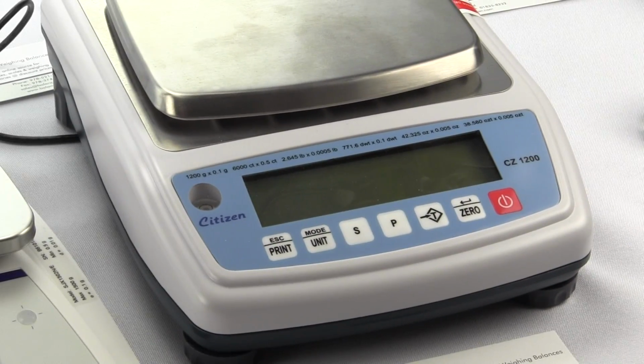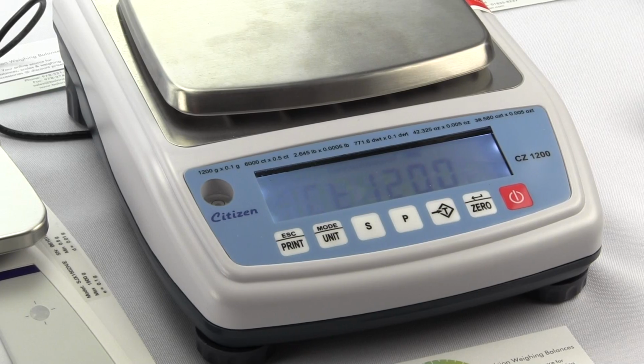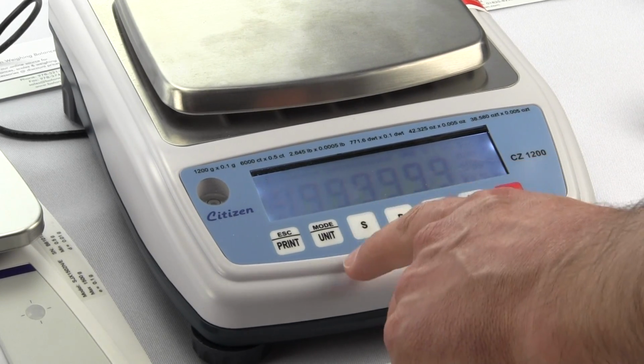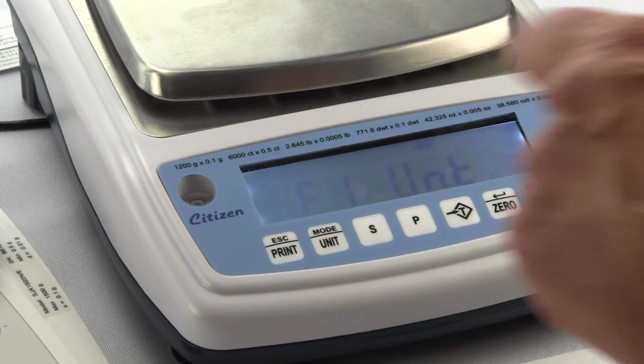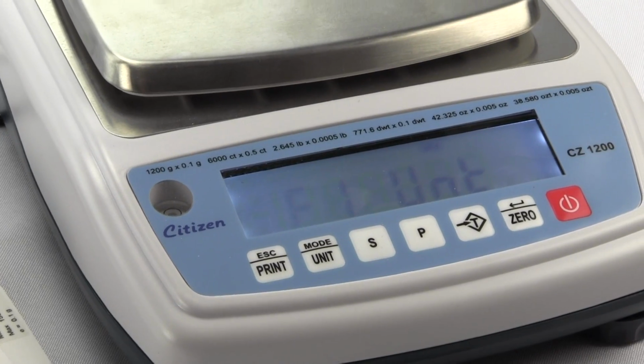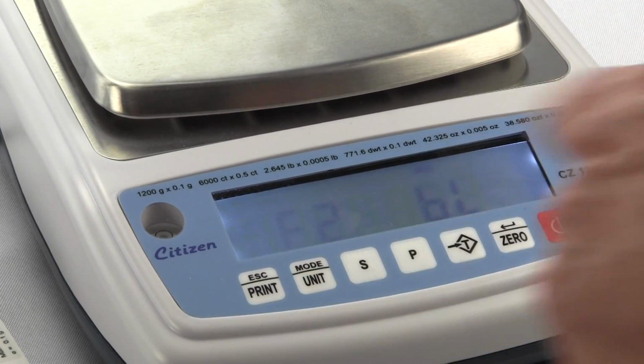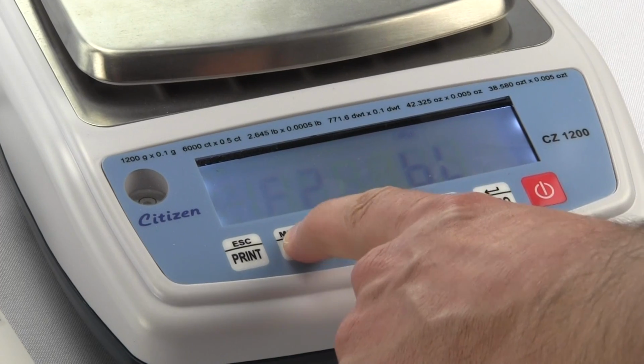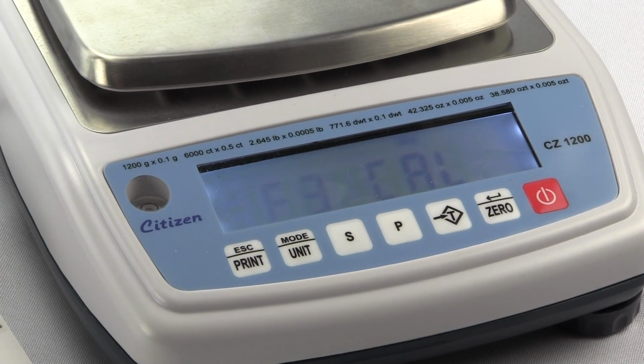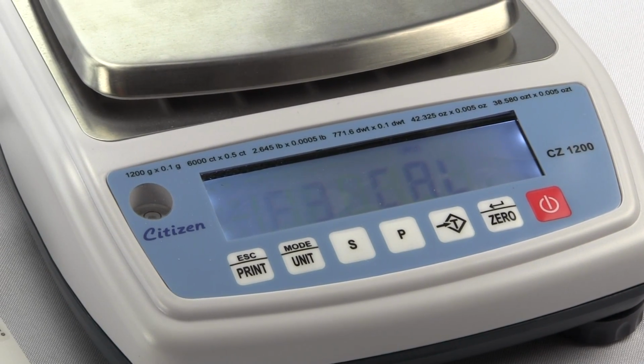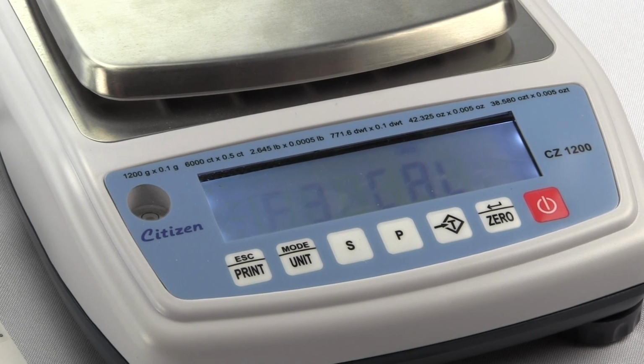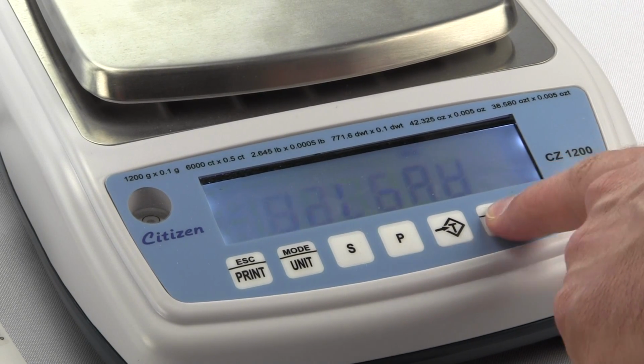To calibrate the scale, you need to turn it on. When it's going down on the power up sequence, we got to hit the mode key. When you hit the mode key, you'll see F1 unit. Hit the mode key again, F2. Hit the mode key again, F3. Then what we need to do the calibration, we need to hit the 0 key.